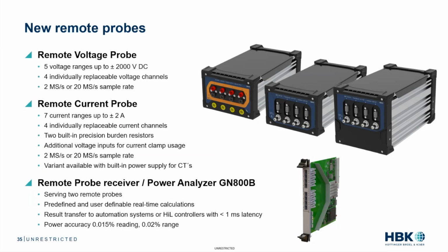But we also have that remote current probe with 7 current ranges up to plus/minus 2 amps, again with 4 individually replaceable current channels, 2 built-in precision burden resistors inside. And you also have additional voltage inputs if you end up using a current clamp for just a quick measurement. Again, same sample rate capability. And then we also have the variant, which is the one on the far right, seen here in the diagram, which has a built-in power supply for the CTs.